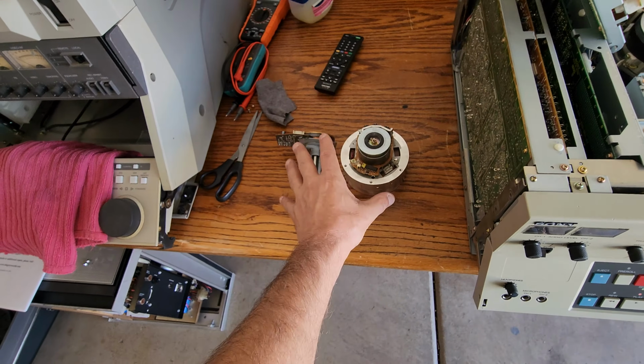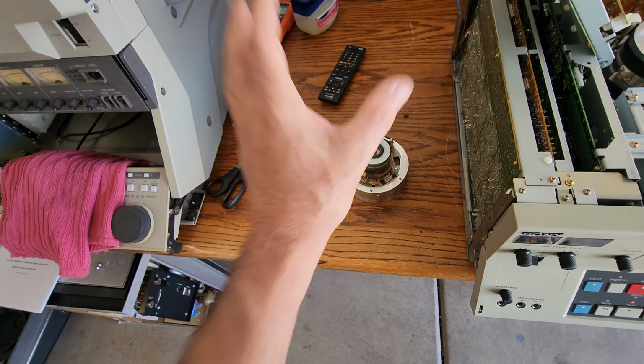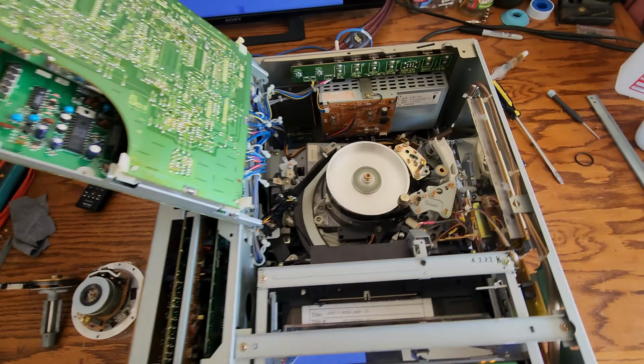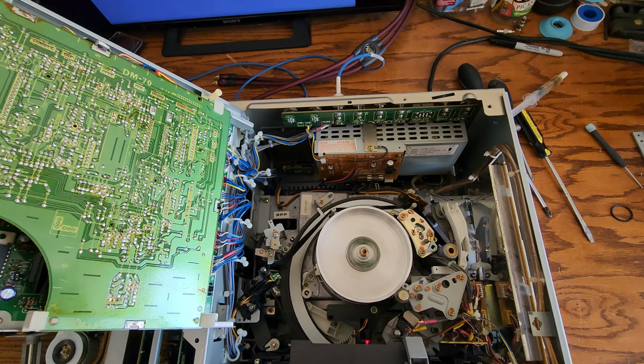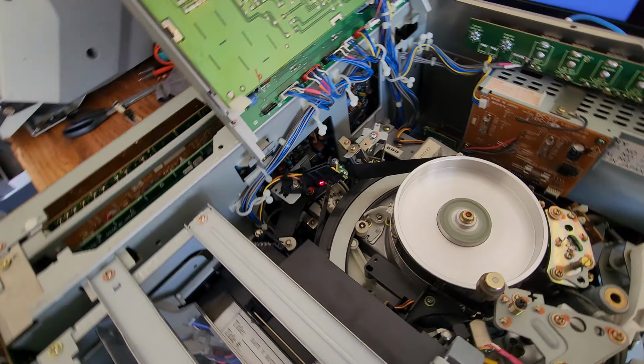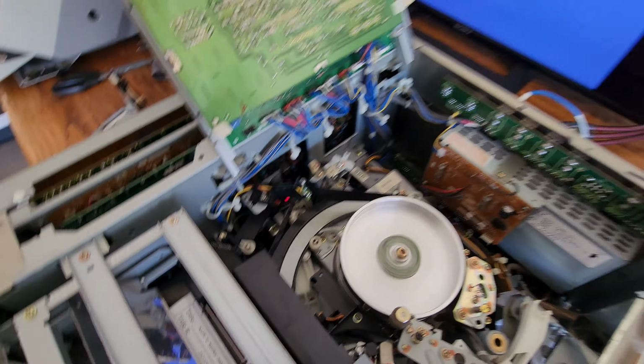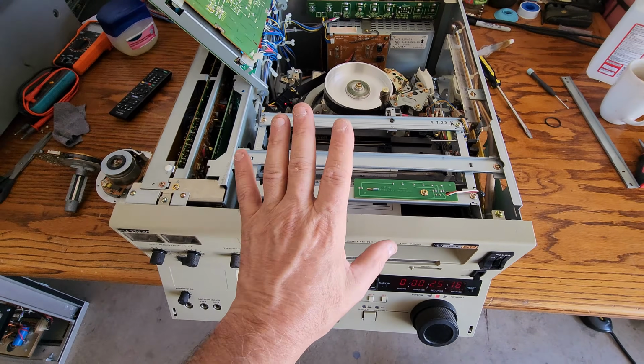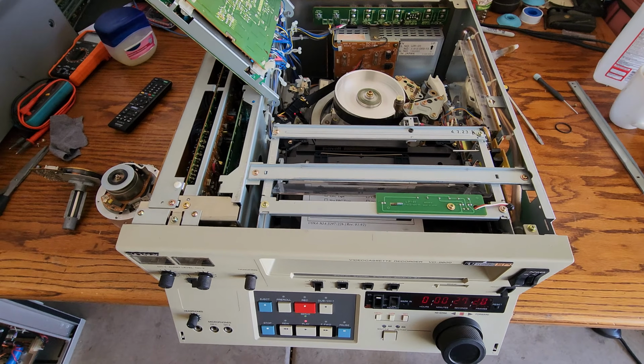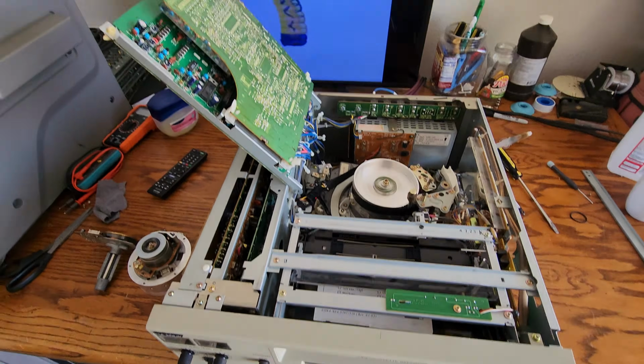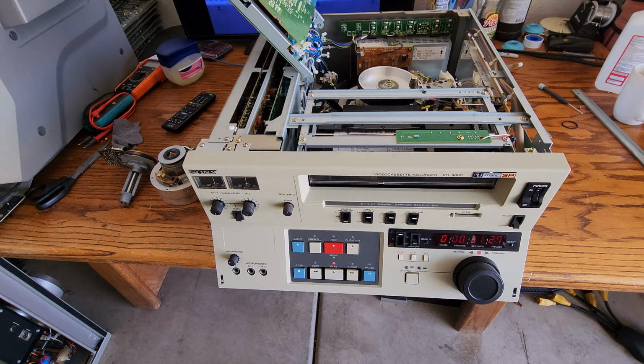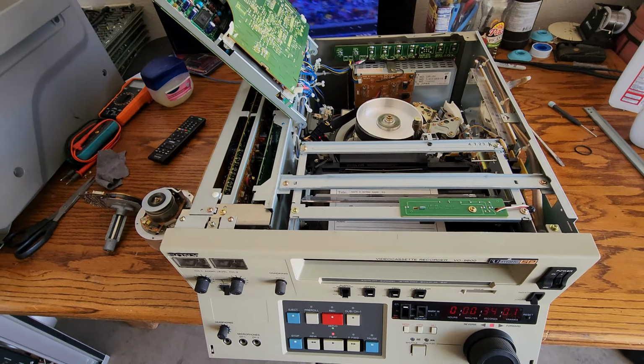So we replaced both a scanner and a capstan motor, and we got that installed, and we did everything else with the roller, and rebuilt the loading ring motor and all that, fixed the loading carriage. I mean, this thing got a serious major overhaul. But since this is one of the higher end machines that everybody wants, they're always worth fixing. But you got to have parts on hand, guys.